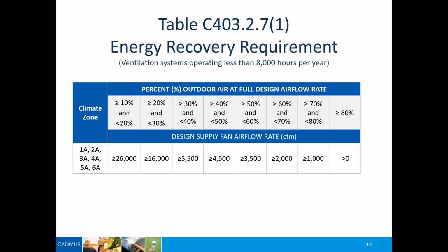So it's a fairly large fan system. But the more outside air I'm bringing in, for example, if I'm at above 60% outside air, then my design supply airflow is going to be about 2,000 CFM, and anything above that, I need to provide energy recovery ventilation on that. If I... Eric, go ahead.